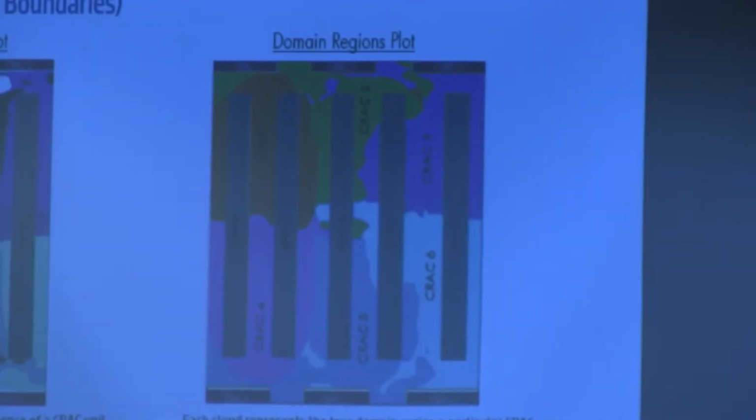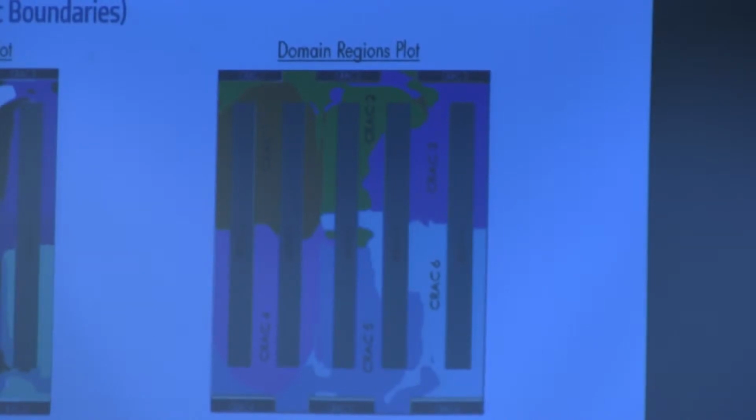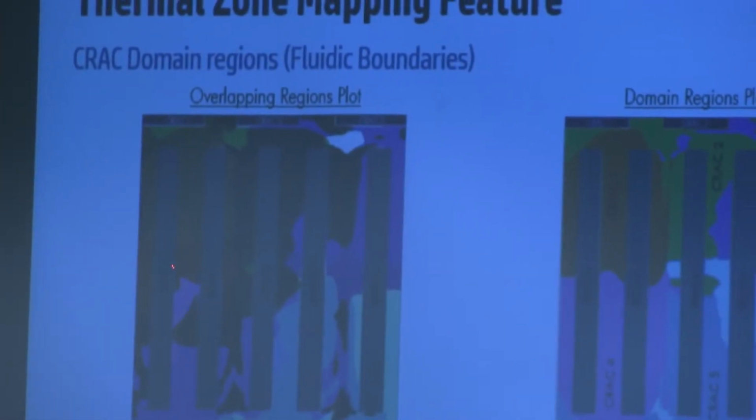And what it gives you is that even though, for example, here we have 2 air handling units that affect the temperature on that region, really the CRAC unit on the top is the one that has the strongest influence. So if you want a faster response on that region, if you have problems in terms of temperature, you go first to that air handling unit, and then you can go to your second unit. So you can generate this geographic kind of plots, right?